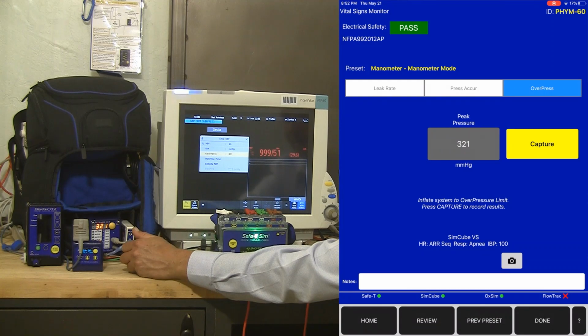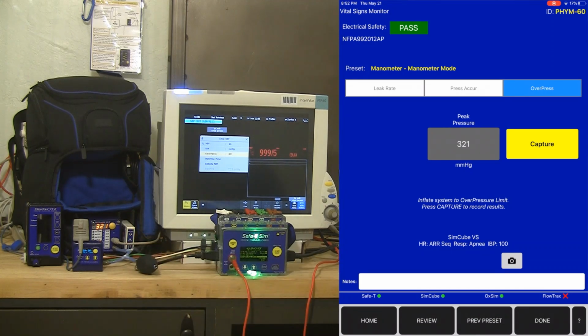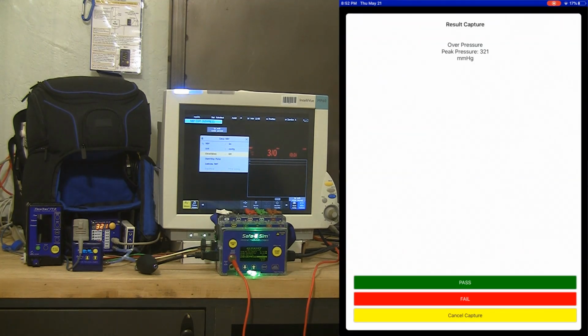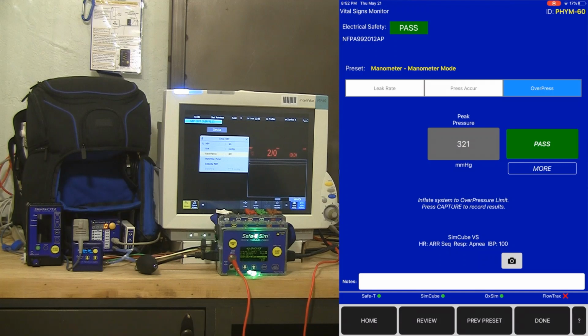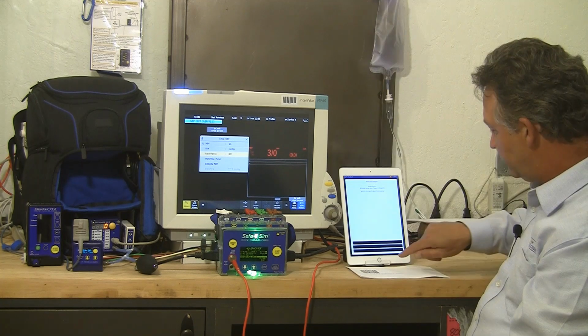Now I'm ready to do an overpressure test, so I'm going to inflate the system higher and look at my peak pressure when the vital signs monitor dumped the pressure for the overpressure limit. We can see the peak pressure was captured by the iOS device because of that real-time data coming from the sim cube via the Bluetooth communications. I hit capture. I've now got my peak pressure at 321 captured. That's a pass, and I am done.